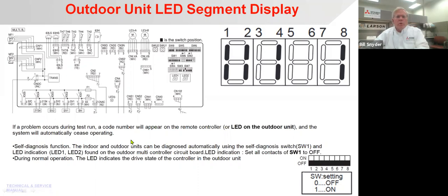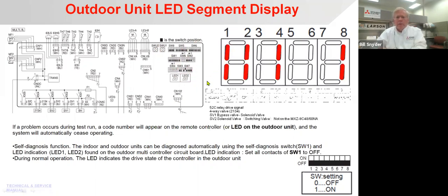Okay, the outdoor unit, this is the MXZ8B, the ones with the branch box. The outdoor unit here, right in here are all the dip switches, and right under here is this LED display that we're going to talk about real briefly. When you first turn the equipment on, these lights light like this, and these are segments. This is segment 1, segment 2, segment 3, 4, etc., as they're labeled here across the top. In this case, it looks like 1111. And I've gotten a number of calls where guys say, I've got an error code of 1111. That probably is normal. This last one is always lit if there's power to it.